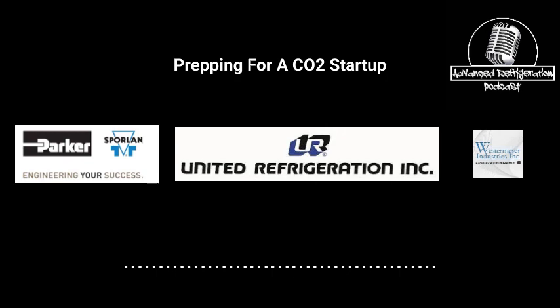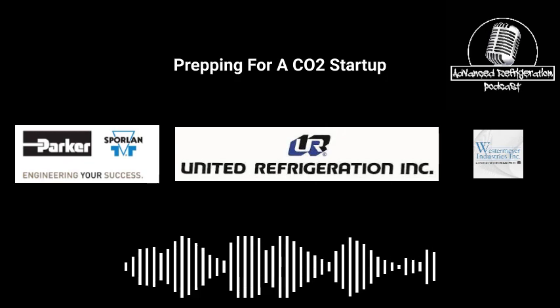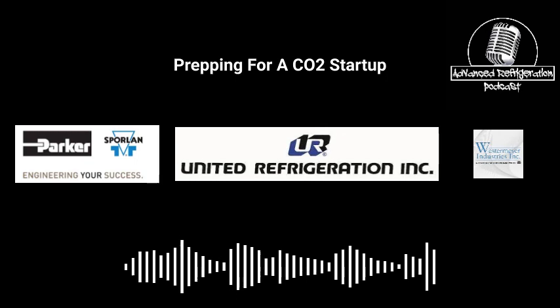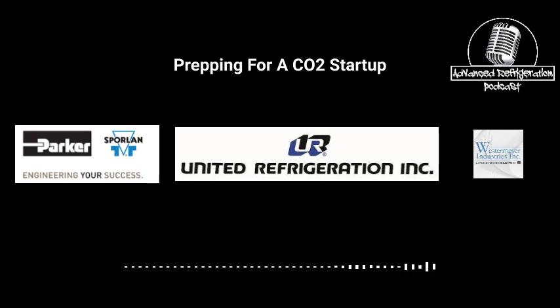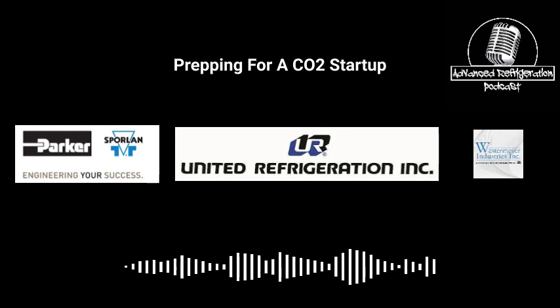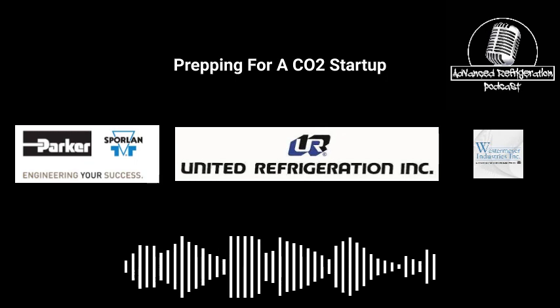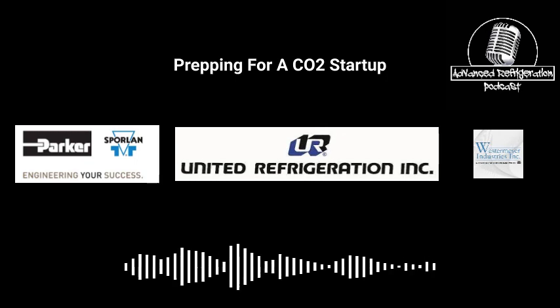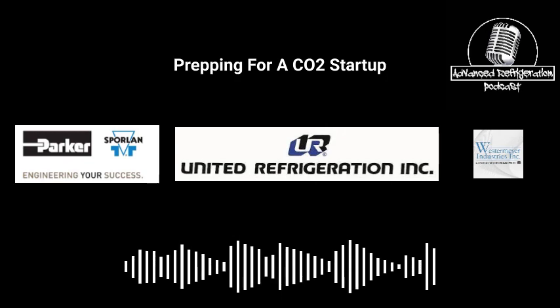It's really loud. So I'll go through all that. And then next thing I'm going through is making sure all my ball valves are open. Make sure I go through the whole rack. Make sure every ball valve that's supposed to be open is open, and the ones that are supposed to be closed, I tag them with tape. I'll wrap them with blue or red tape. And I will go through all the ball valves.